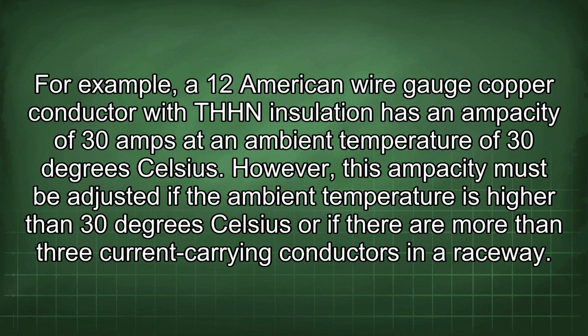For example, a 12 American wire gauge copper conductor with THHN insulation has an ampacity of 30 amps at an ambient temperature of 30 degrees Celsius. However, this ampacity must be adjusted if the ambient temperature is higher than 30 degrees Celsius or if there are more than 3 current-carrying conductors in a raceway.